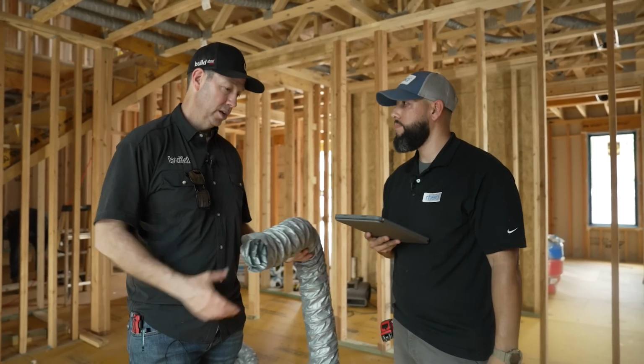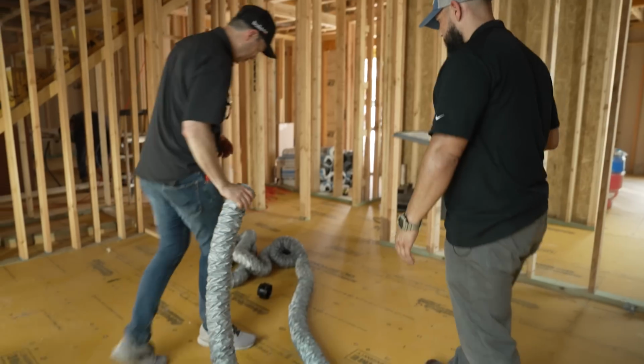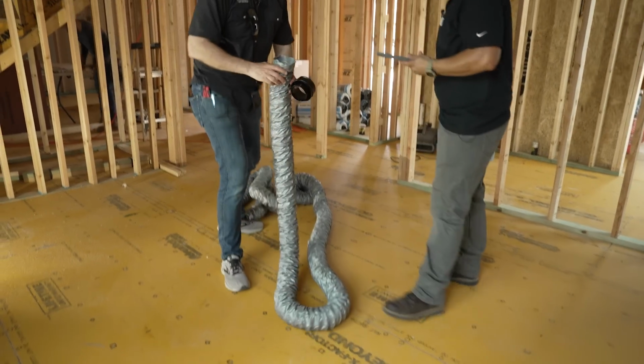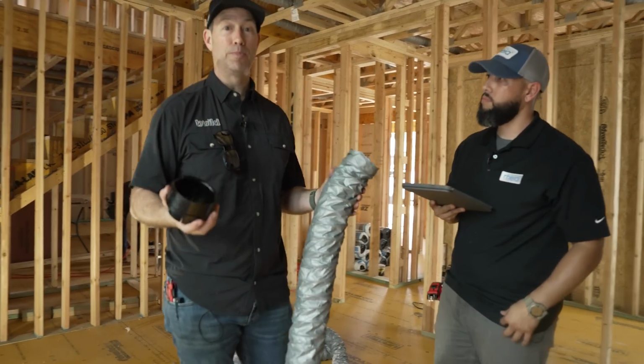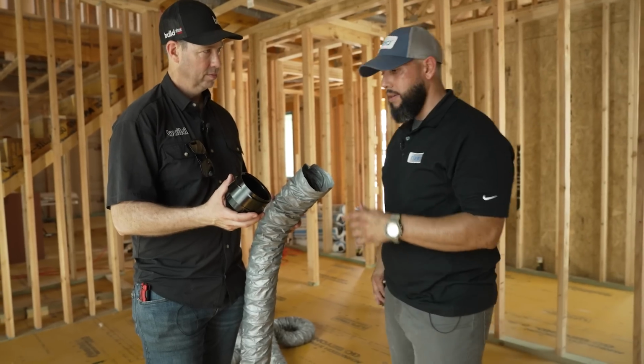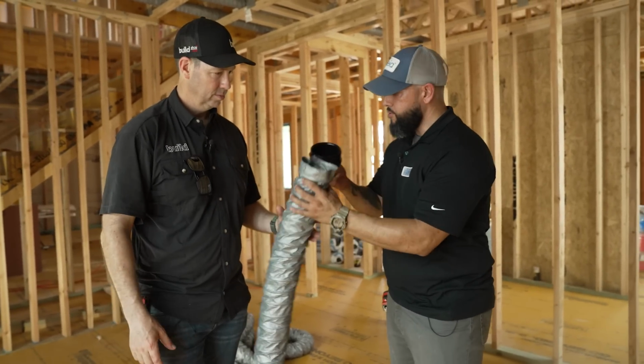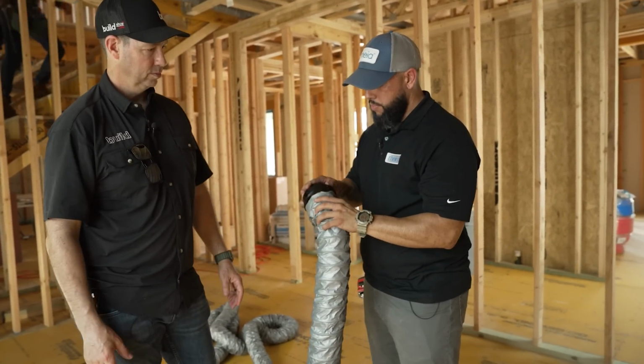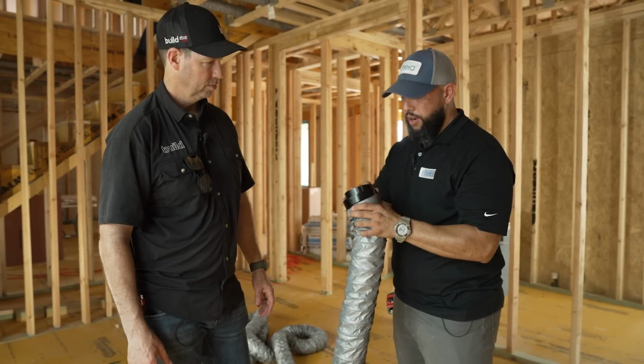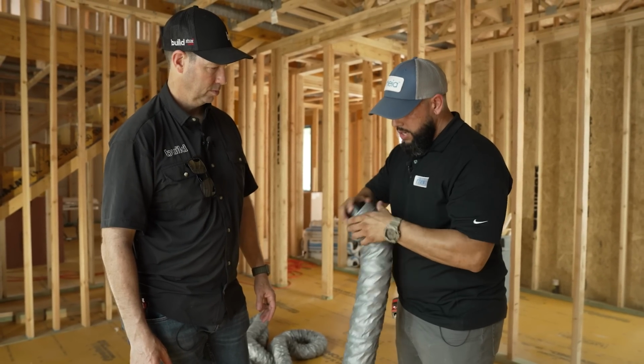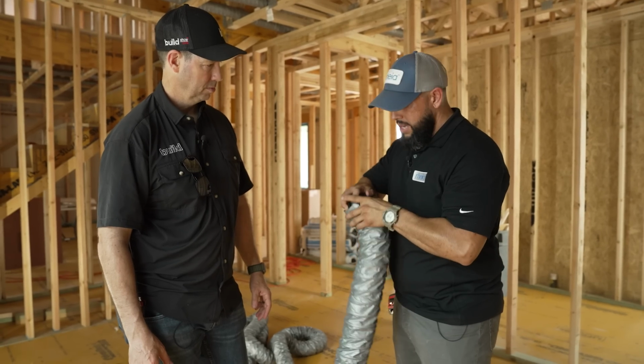One thing that blew my mind is that on a job site with Rheia, I didn't see any tape or mastic being used. Explain how you get an airtight connection. We have no duct tape, no mastic, no zip ties, no screws. We use this threaded component, one of our only threaded parts in the system, this is the 4-inch ferrule, and we've also got a 3-inch ferrule. It threads onto the duct and creates a nice, tight, airtight seal.